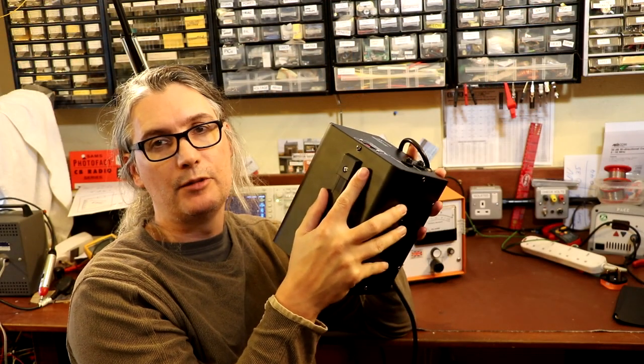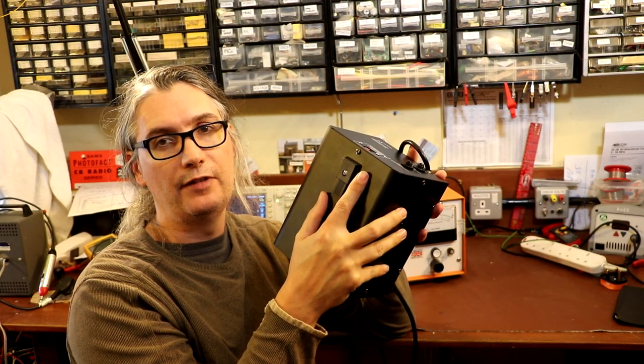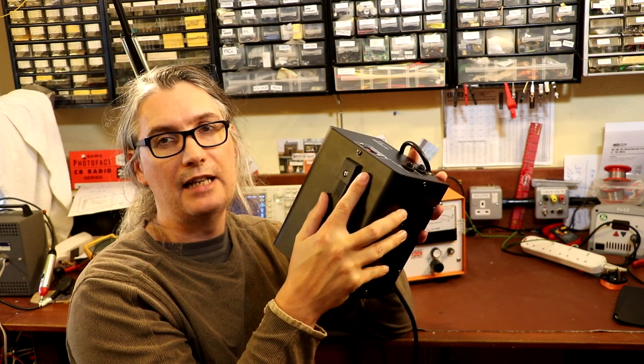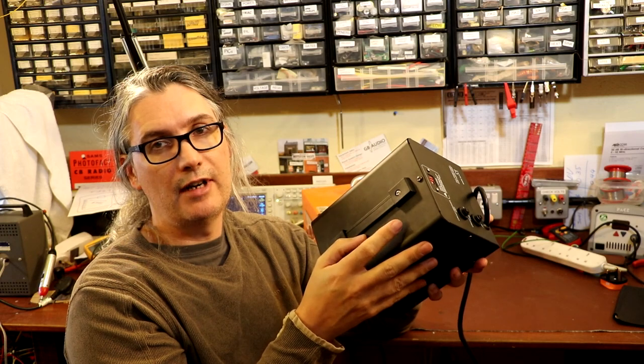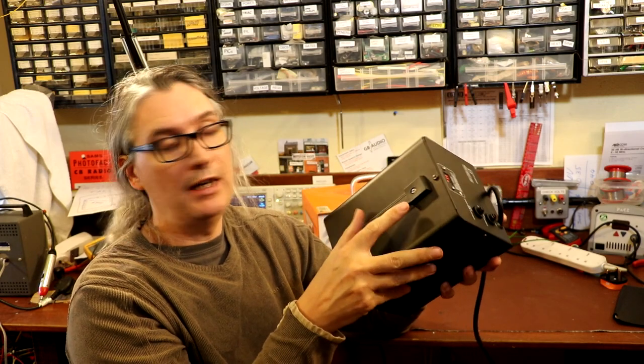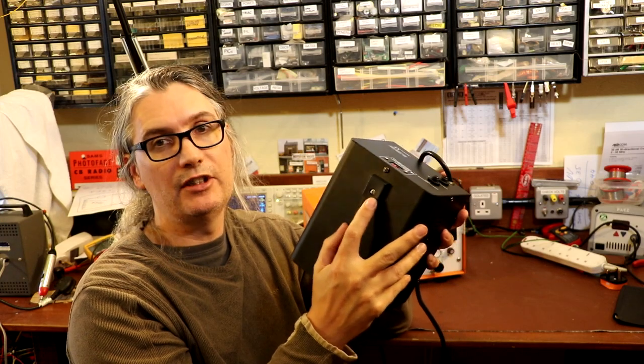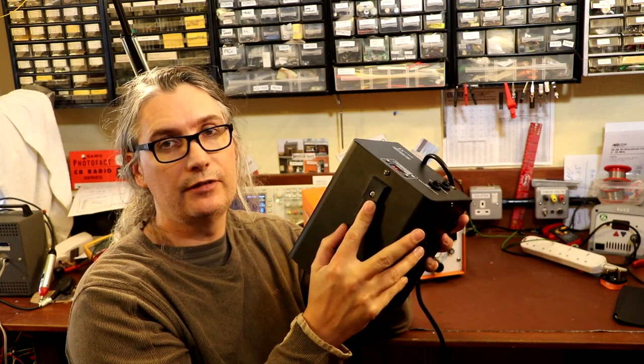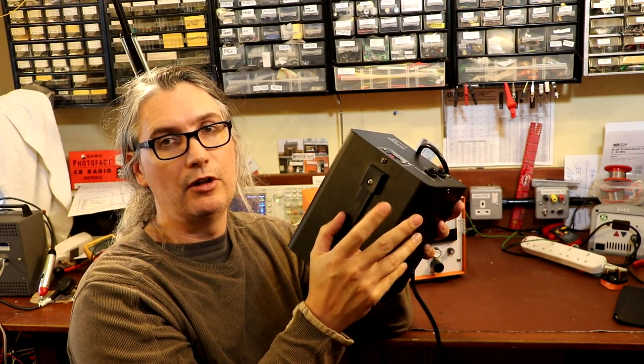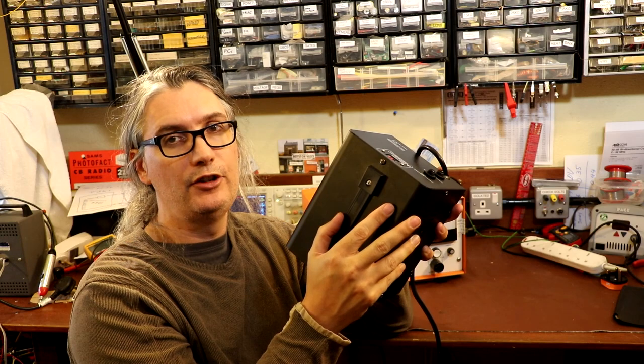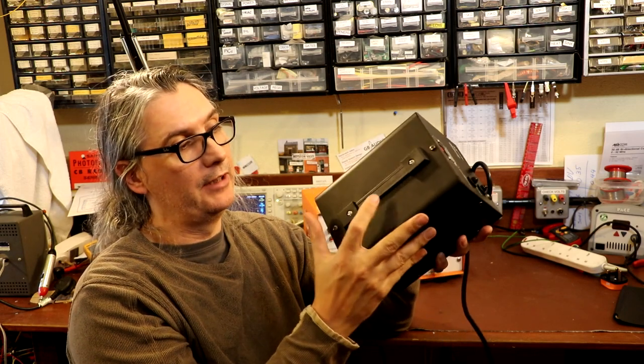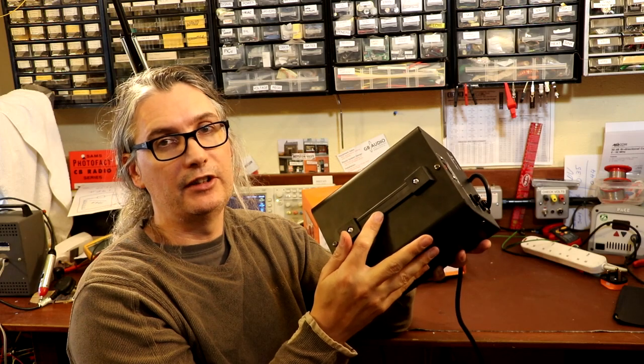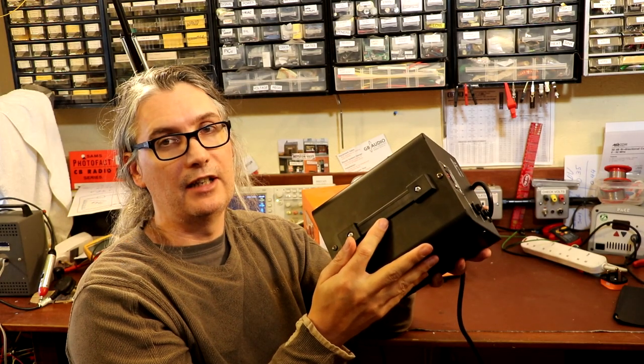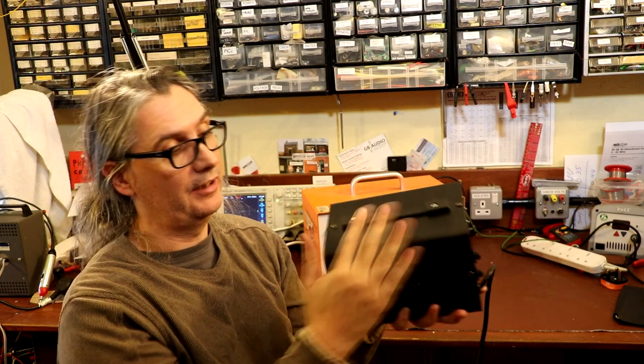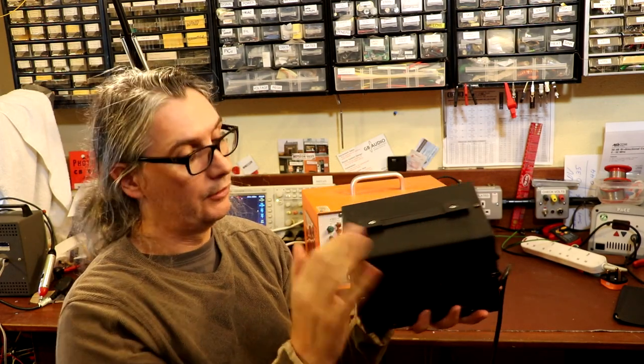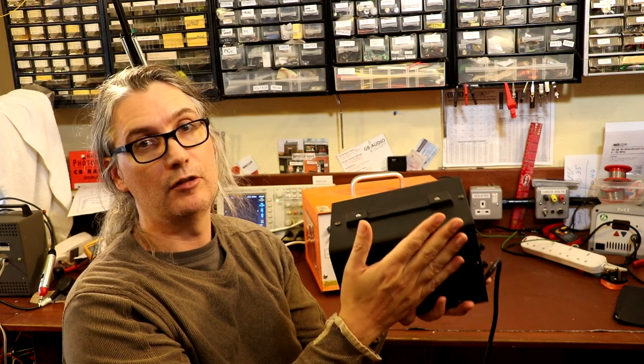Now, having spent about 5 minutes berating the manufacturer for using the bolt that holds the feet on as the main earthing stud, did you see that I went ahead and did something just as stupid? I've installed a strap between the main earthing stud on this top cover, but what I actually fastened it down to was this bolt here, which is actually designed to hold the handle on. I shouldn't have done that. What I should have done is drilled a separate hole in this top cover and fixed a bolt on there just for the purpose of earthing. Because somebody might, for reasons unknown, decide to take this handle off in the future, and if they do, my earth wire will fall off it. That could leave this top cover unprotected, unearthed. So if a wire comes off and touches the side of the cover here, that could become live.